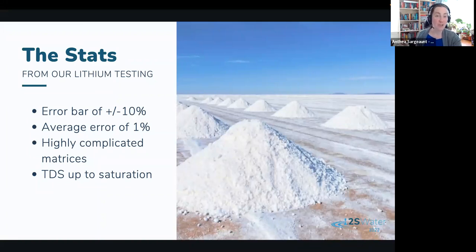The complication of the matrix has not been a significant factor within those, although we are always watching and paying attention to the matrix as it comes along. As I mentioned before, TDS up to saturation has been handled by the machine very well. What we do try and avoid is either hydrocarbons or high levels of TSS coming through the machine. They don't affect the analysis in terms of the data generated—where we worry is around clogging and fouling of the sensor. So at this point, we are trying to look for those applications that are low TSS and low hydrocarbon.